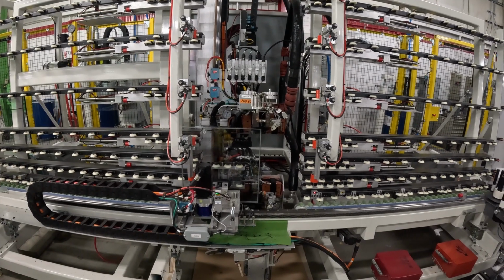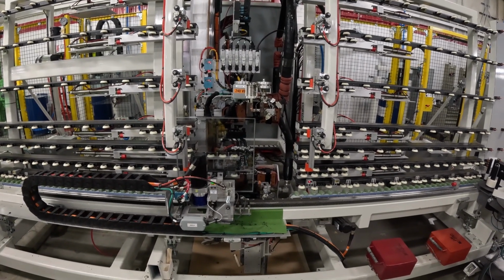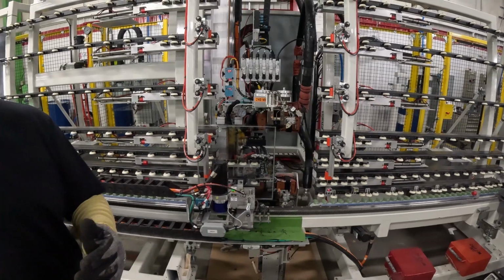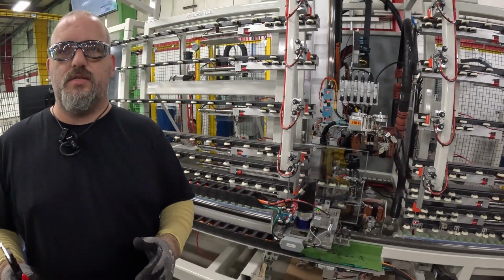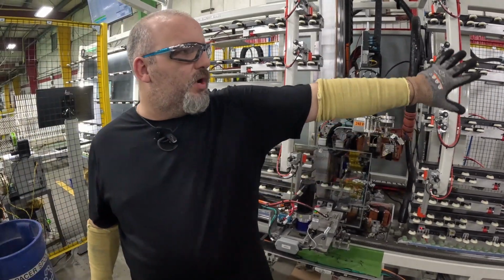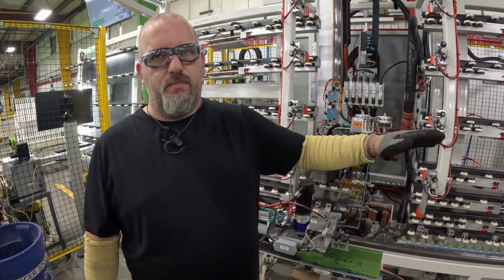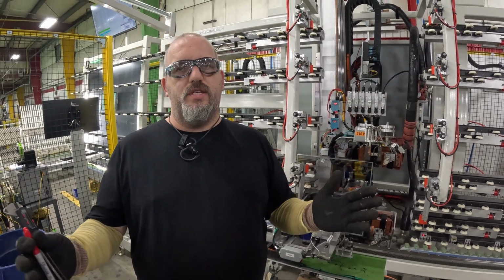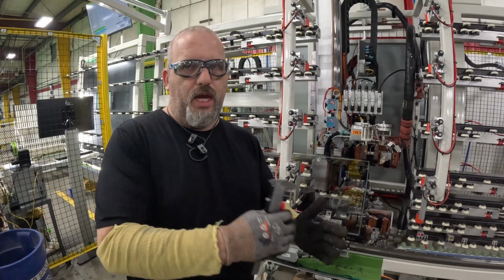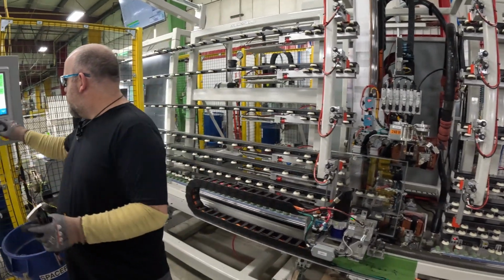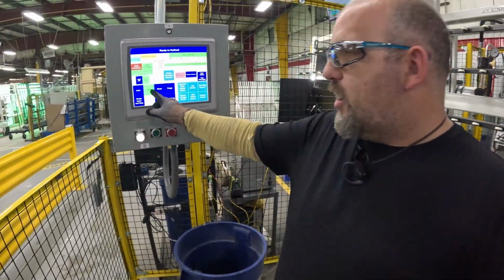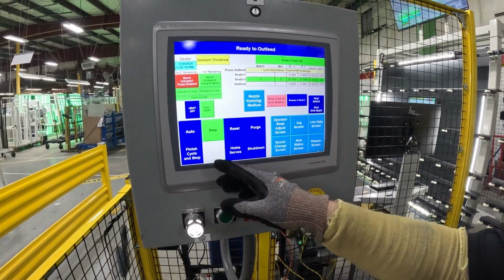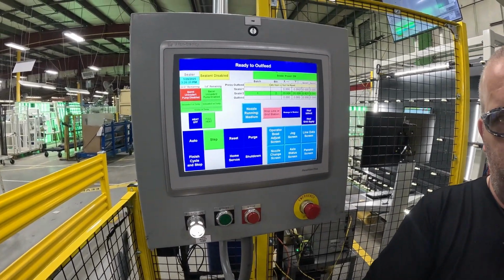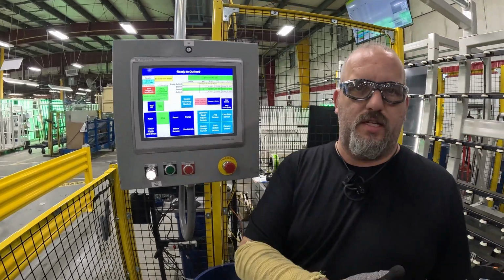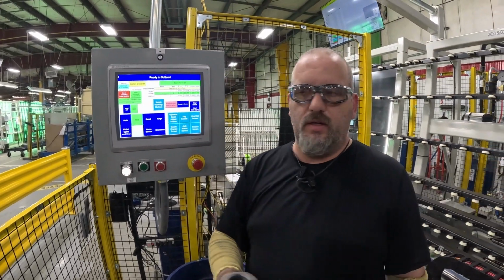And you're just hitting start until it comes up the other end? Yeah, all step mode does is cycle through the process. From the beginning of the process of this entire machine in auto, there might be like 40 steps to go from beginning to end. Step mode is just like auto in the fact that instead of just it automatically cycling through everything, it breaks it into steps so you can watch what's going on.